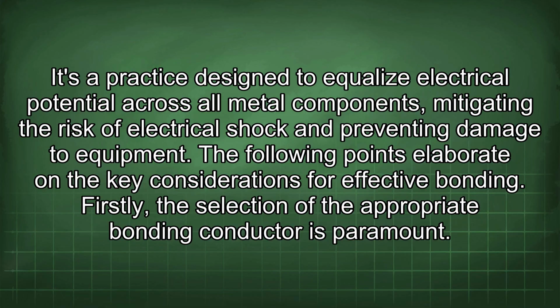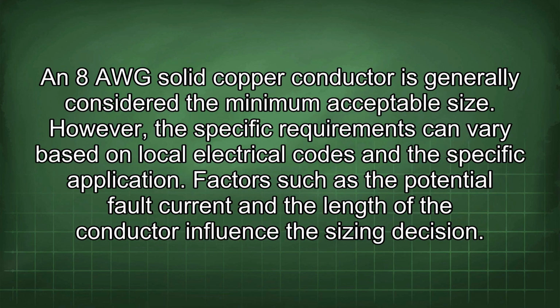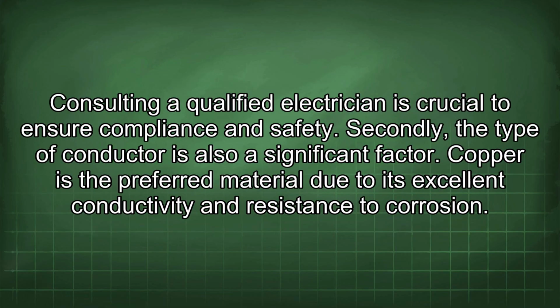Firstly, the selection of the appropriate bonding conductor is paramount. An 8 AWG solid copper conductor is generally considered the minimum acceptable size. However, the specific requirements can vary based on local electrical codes and the specific application. Factors such as the potential fault current and the length of the conductor influence the sizing decision. Consulting a qualified electrician is crucial to ensure compliance and safety.